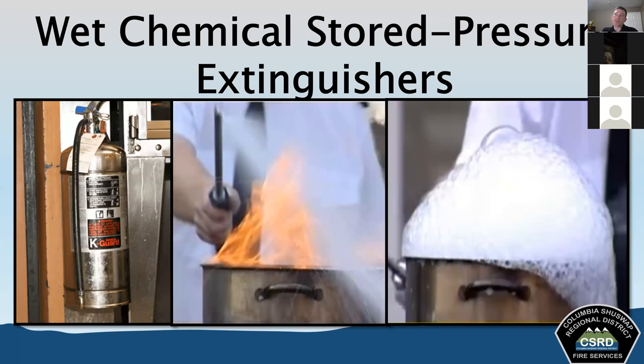Wet chemical stored pressure extinguishers are similar in appearance to stored pressure water extinguishers, but are intended for use on class K fires. These contain a special potassium-based high pH agent formulated to operate on the principle of saponification — it creates an oily film that goes on top of the burning material and smothers it, removing oxygen from the fire tetrahedron. The agent combines with the oils to create a soapy foam surface over the cooking appliance. Some departments may carry this type, though availability varies.